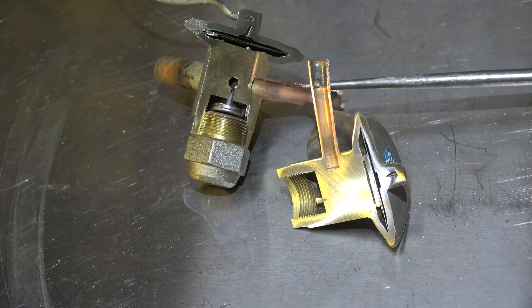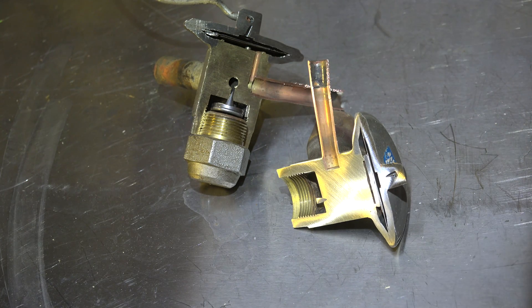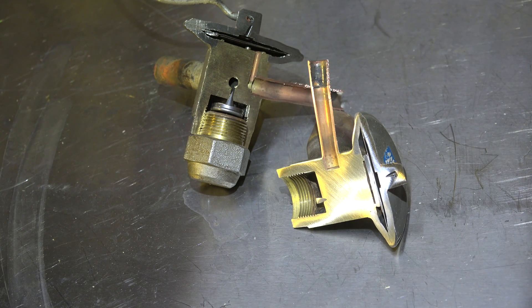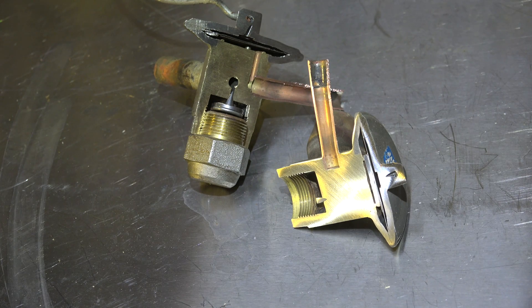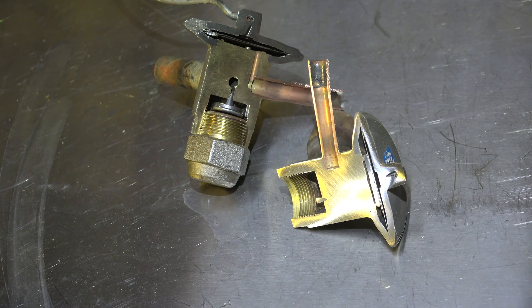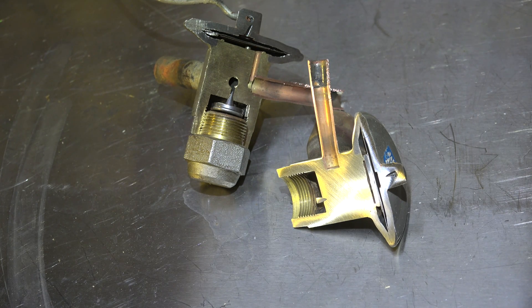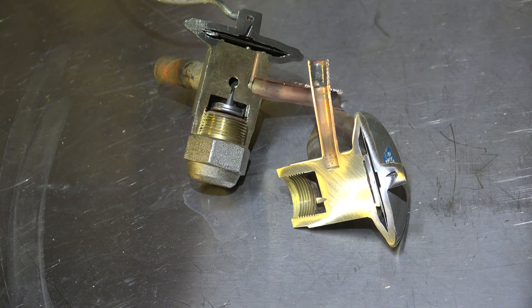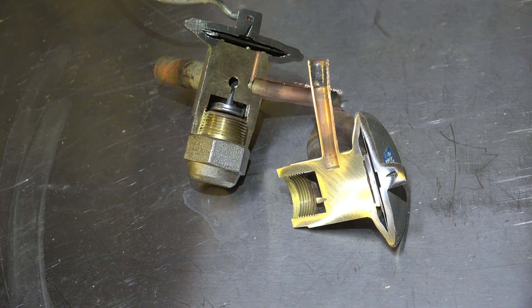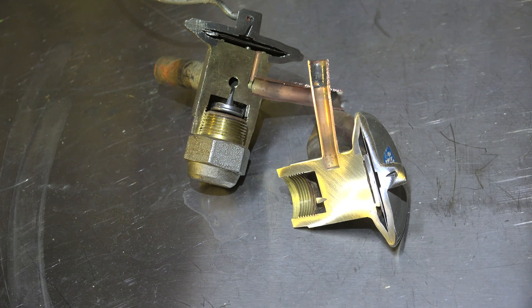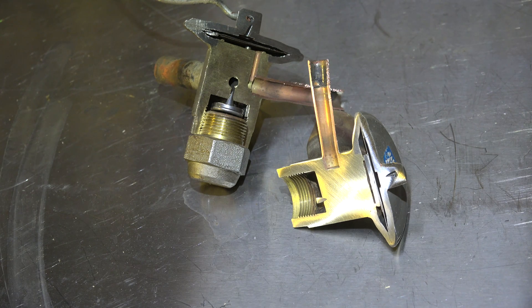This doesn't have anything like that. All it's got is the equalizing tube, and I'm not sure the equalizing tube will move enough refrigerant to make any difference. If I have a bleed TXV, I can use a PSC compressor.